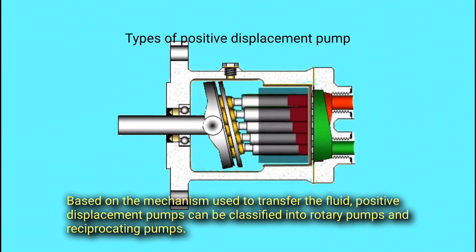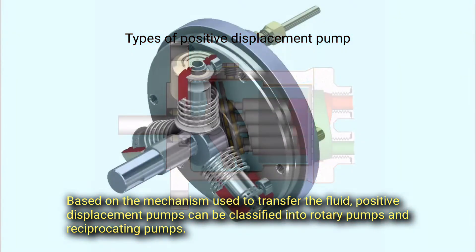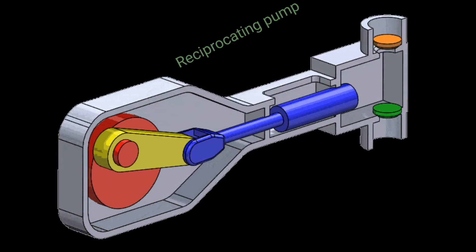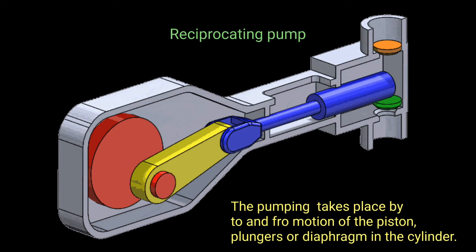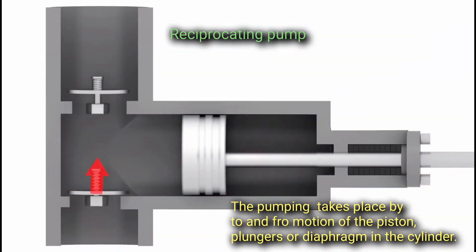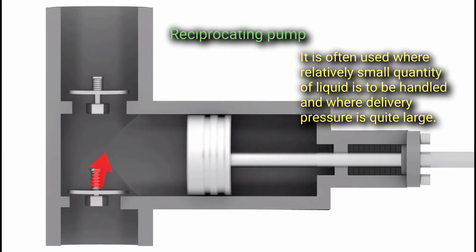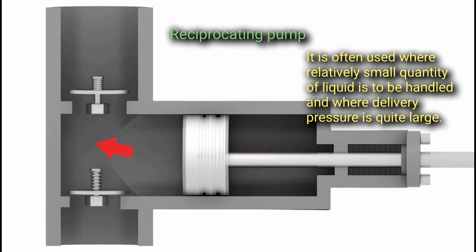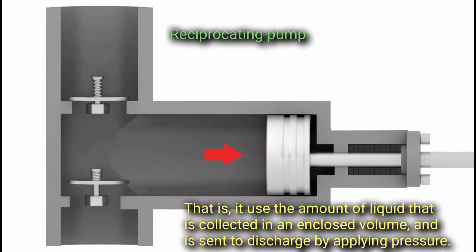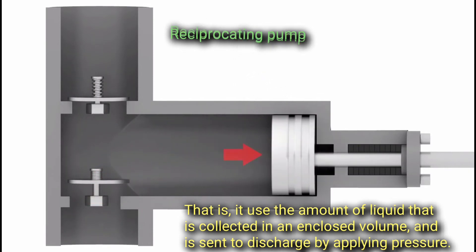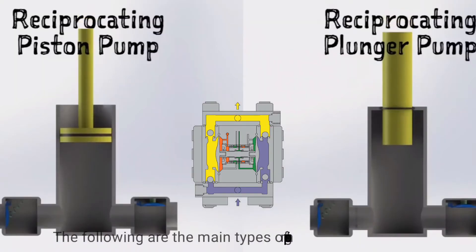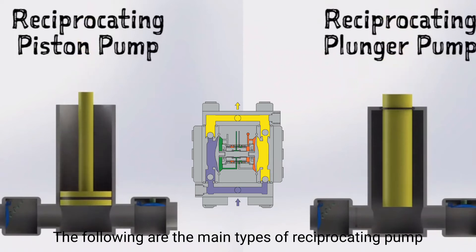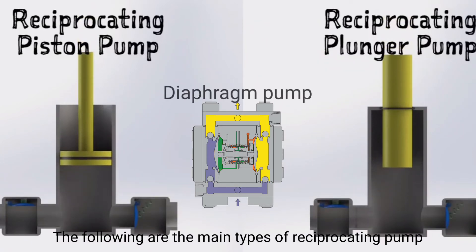Positive displacement pumps can be divided into rotary pumps and reciprocating pumps. In reciprocating pumps, pumping takes place by the to-and-fro motion of a piston, plunger, or diaphragm in a cylinder. They are often used where a relatively small quantity of liquid is to be handled and where delivery pressure is quite large. The main types of reciprocating pumps are: piston pumps, plunger pumps, and diaphragm pumps.